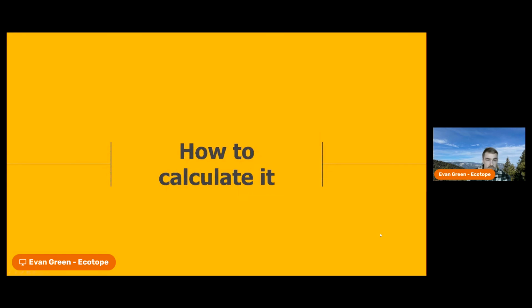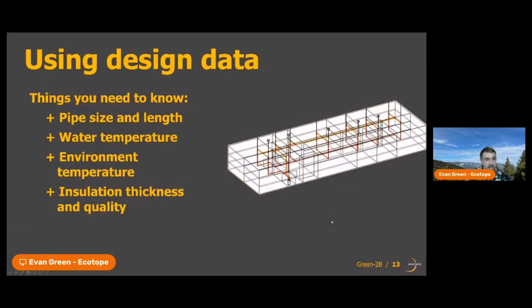So in order to calculate these heat losses in a design that hasn't been built yet, we can't put monitoring equipment on the pipes because they're not there and we don't have hot water flowing yet. But what we can do is look at the design drawings themselves and pull some necessary data to calculate these heat losses. The first thing we'll need to know is the pipe size and the pipe length, because we need the overall surface area that heat is being transferred through. And Christoph mentioned that it's just heat leaving this water and transferring through the pipe wall and the insulation into the surrounding environment.